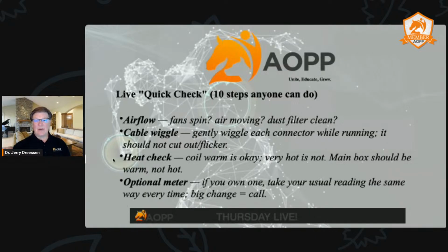Optional meter. If you own one, take your usual readings at the same time, the same way every time, and be consistent on that. If there's any changes, call. Some people do have a Gauss meter, but these things are very sensitive. If you talk to any manufacturer, it's actually a huge expense to put it in a room that's totally magnetic free, because you need to have absolutely no magnetic variance anywhere, including Earth's magnetic field, in order to get a true reading.